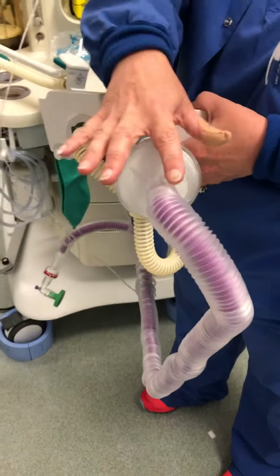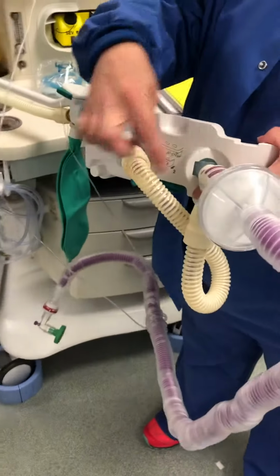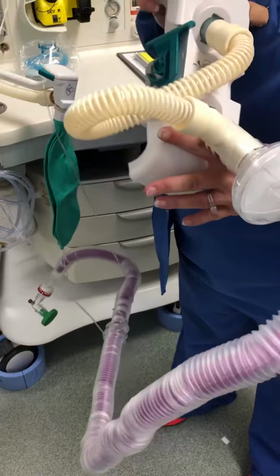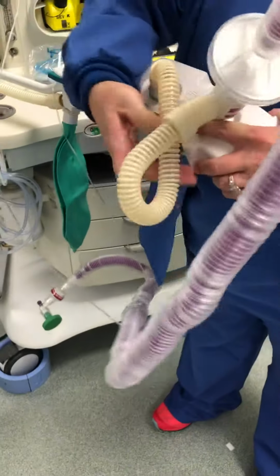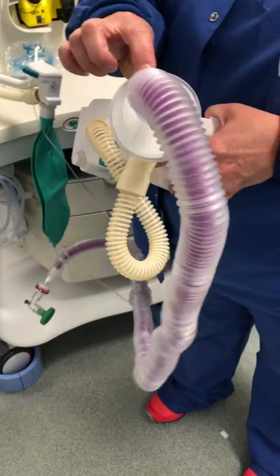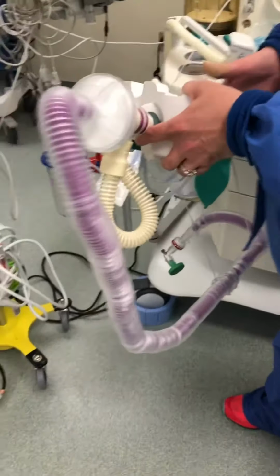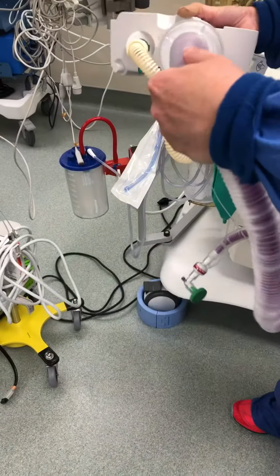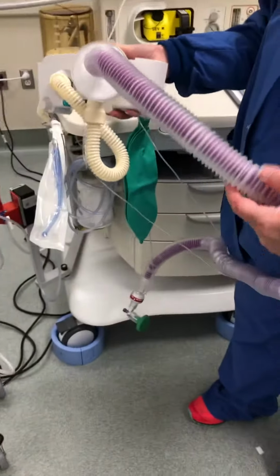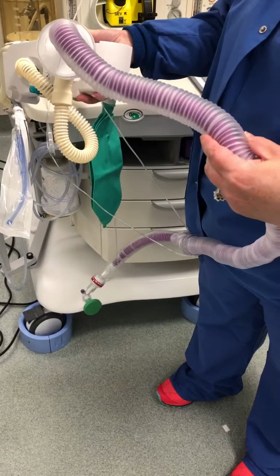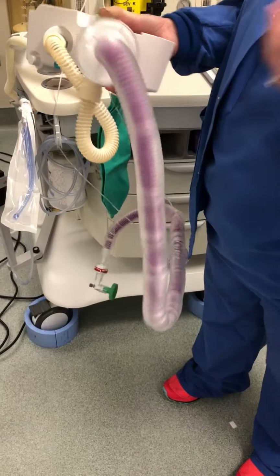With the patient circuit, look at the corrugated tubing and the manifold, and make sure they don't have any visible cracks or holes. Then look at the patient circuit. You want to just visually see if there are any cracks. A lot of times you can just change the patient circuit, and most of the time that corrects the leak.